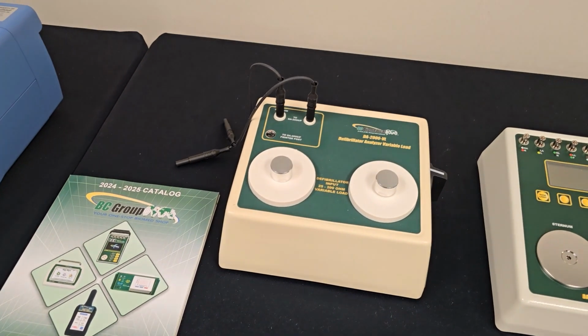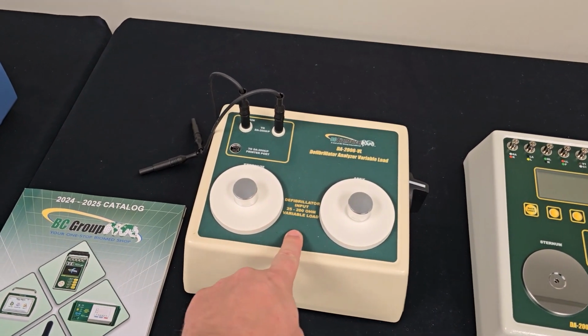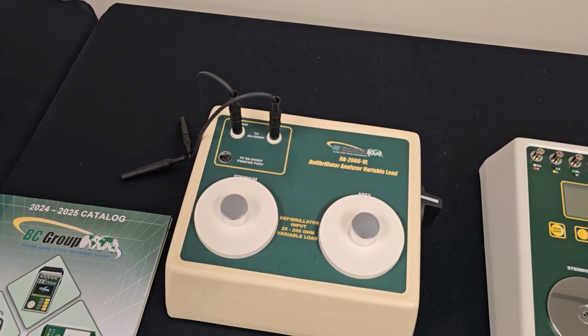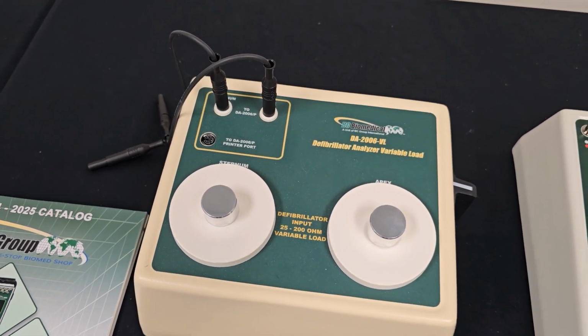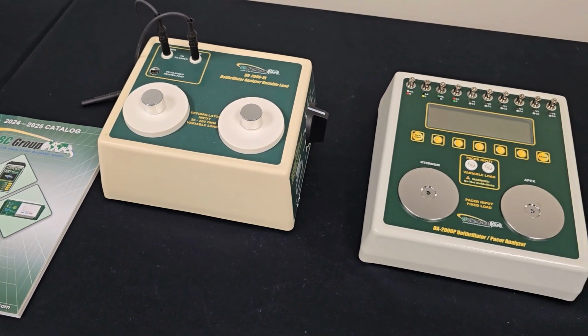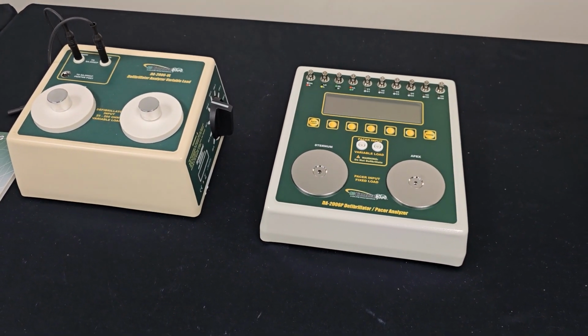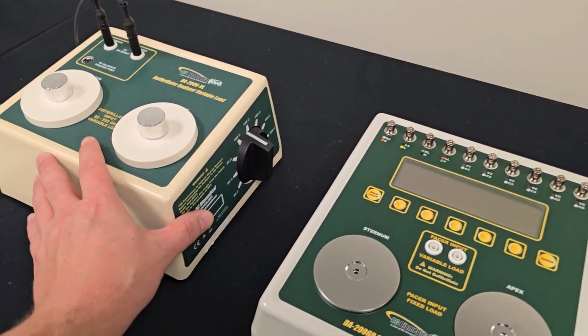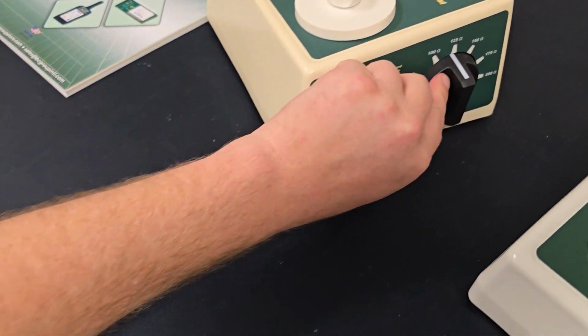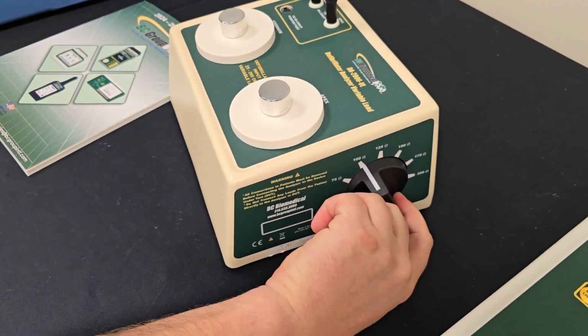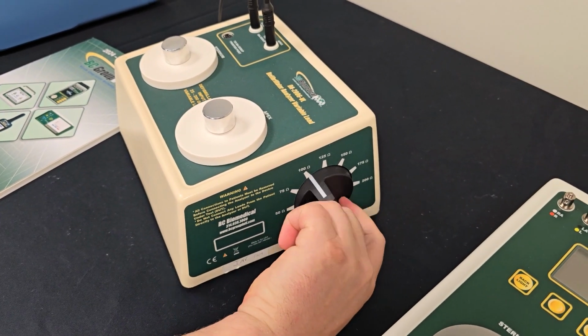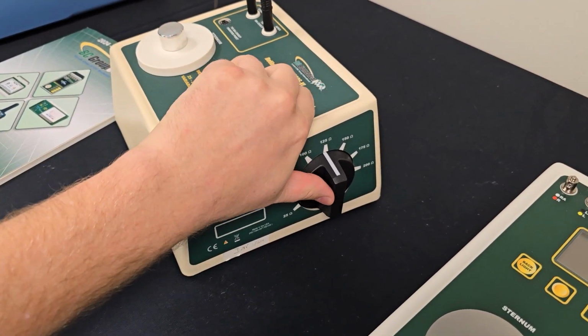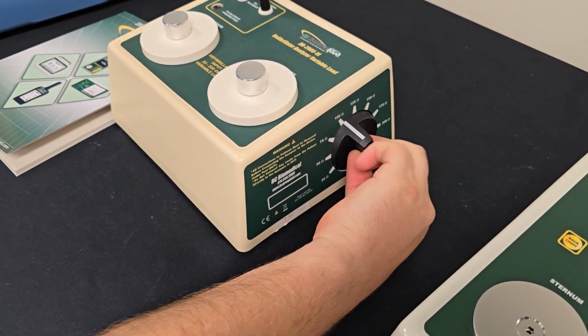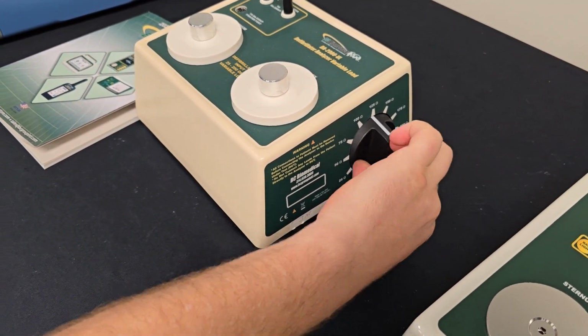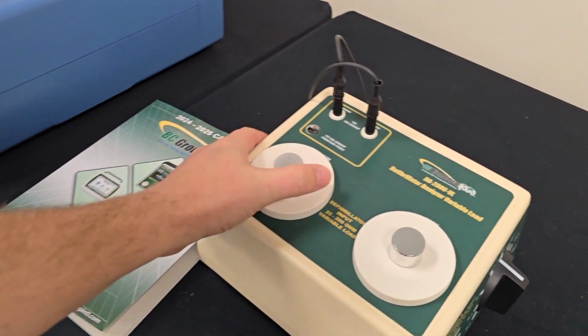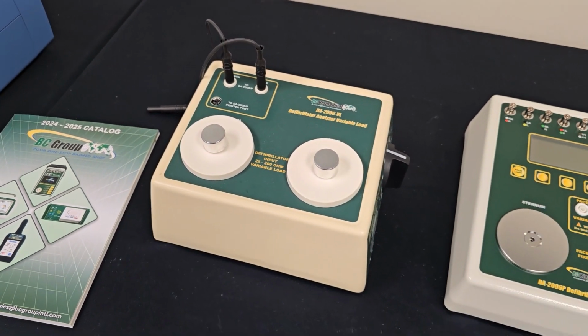And I've not seen this guy before either. So that's a variable load for the defibrillator analyzer. A lot of the OEM testing, the manufacturer of the defibrillator itself, the standard requires them to test at multiple loads. So the typical Biomed doesn't need that unless they're doing troubleshooting or analysis, trying to figure out what's a problem with the defibrillator. Oh, that's got an old school ka-chunk type of click. That's very satisfying. Well, imagine 360 joules. You've got a lot of current passing through there. So yeah, it's a big beefy switch.